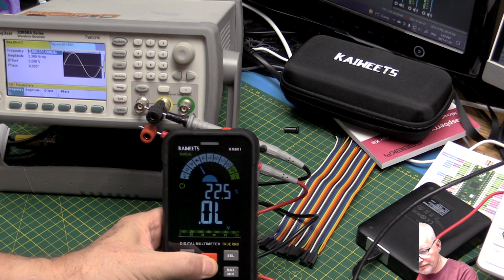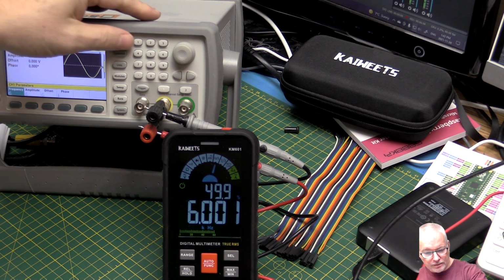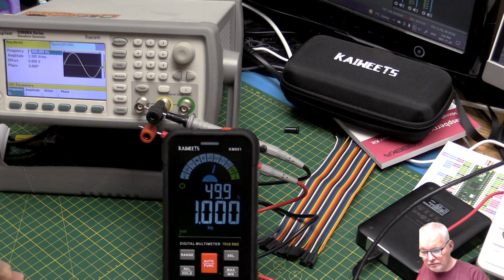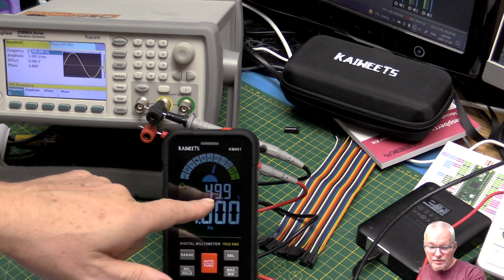So now what we will do though is we'll go to the frequency range and see if that's any better, because it claims frequency up to 10 megahertz basically, with an accuracy of 1%, plus or minus 3 counts. Sorry, plus 3 counts, there's no minus. Yeah, so let's start with 1 hertz. So let's put in 1 hertz, and there we go, 1.000 hertz at a 50% duty cycle.